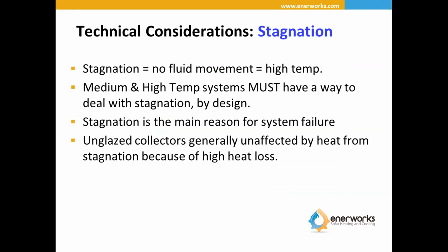So stagnation is essentially when the system overheats. This could be because a pump failed. In domestic water systems, it could be as simple as the city shutting water off to the building. It could be a loss of electricity. There's a number of different reasons why this would happen. And if you've oversized the system, stagnation can occur when you've heated up the domestic water tank.